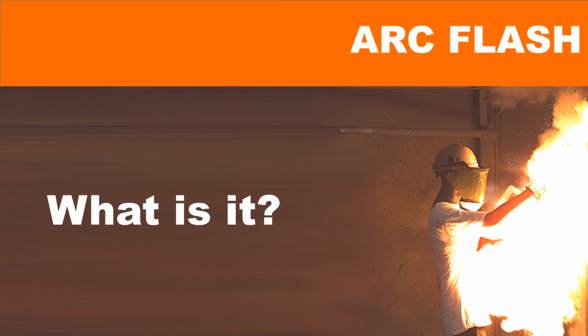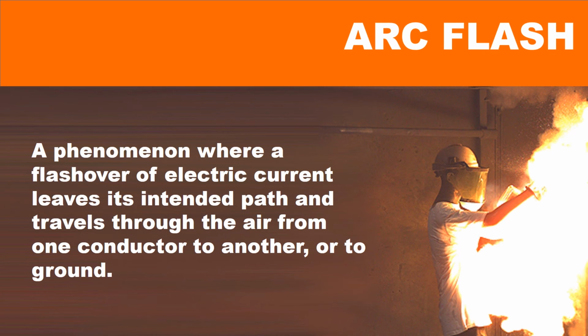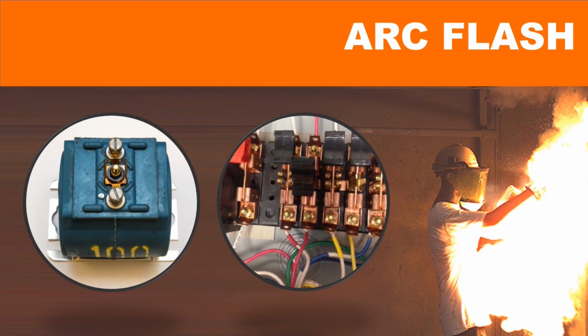Simply put, it's like a dam full of water bursting and rushing uncontrolled across the land. Except arc flash is so hot it melts metal and even reaches plasma states. You're most likely to see arc flash occur when removing a transformer-rated meter for testing. Be sure to engage the shunt bar of the CTs before you remove a meter.